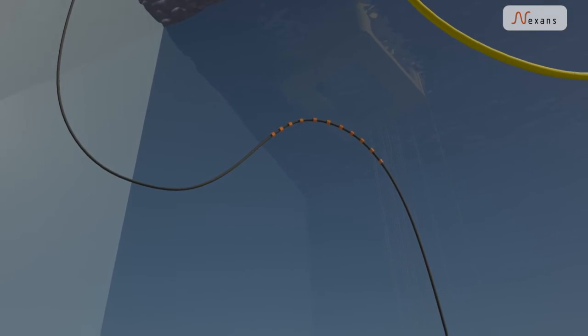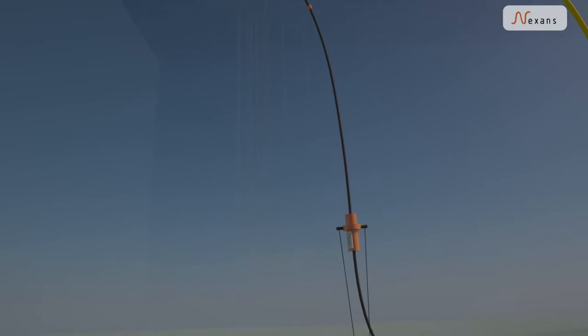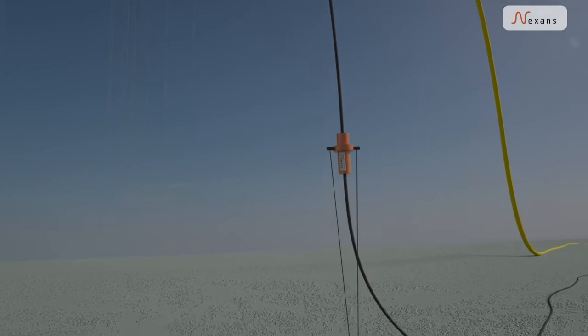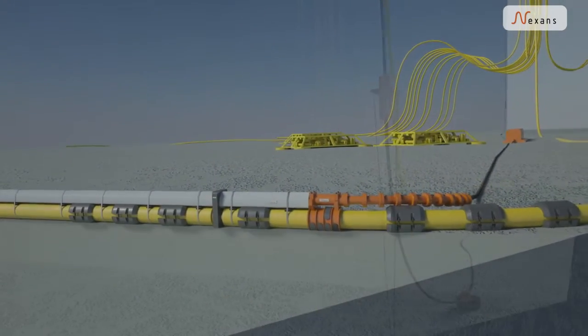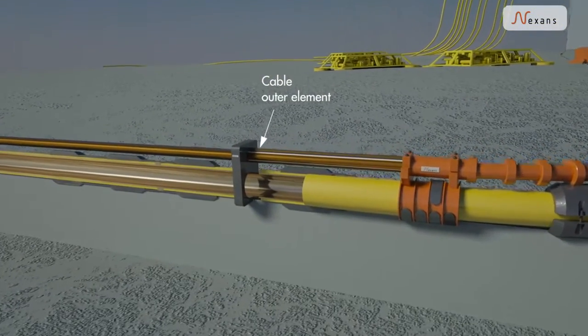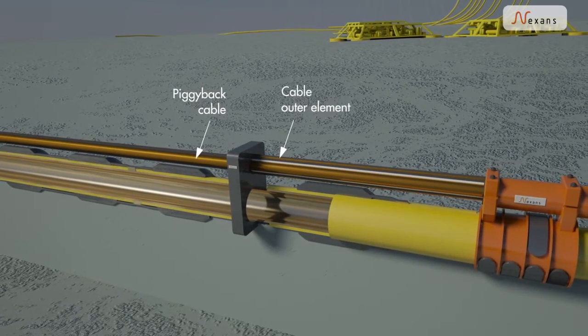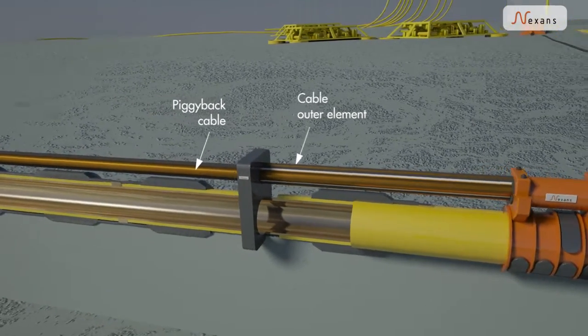A high voltage riser cable is led down to a subsea junction box and further on to the pipeline near end. Here, the riser cable's outer element is connected to the pipeline. The central core of the riser cable is connected to a piggyback cable, which is strapped on top of the pipeline.